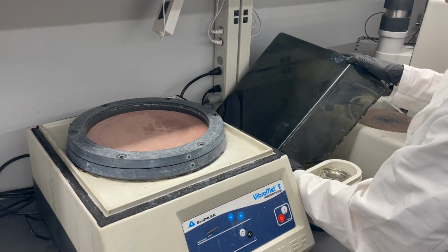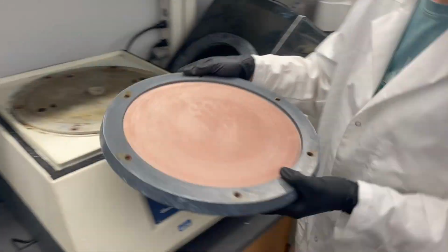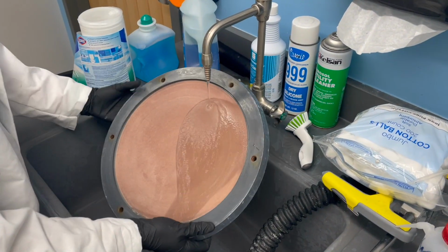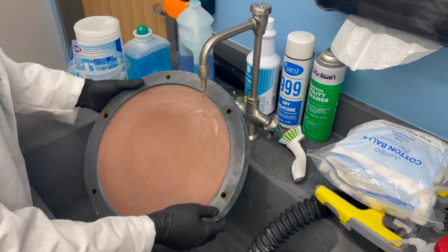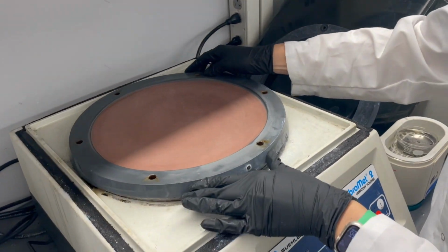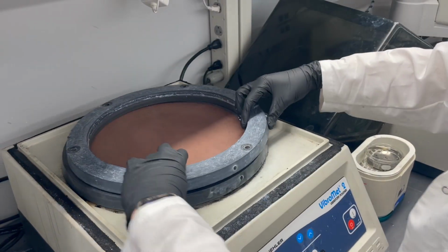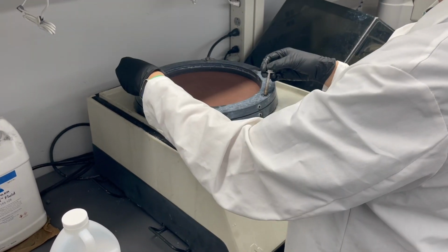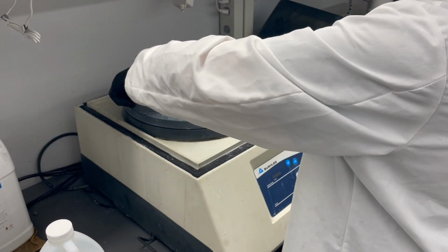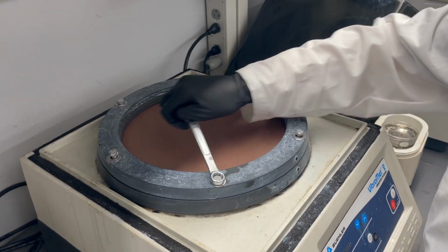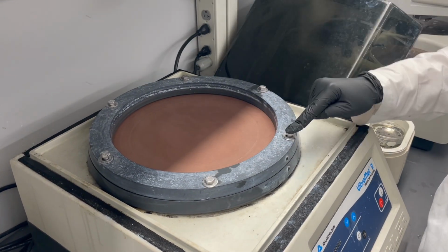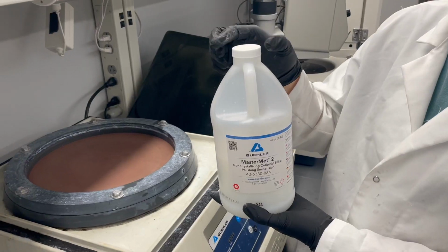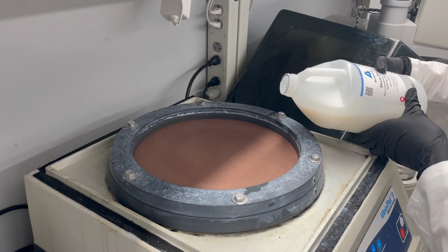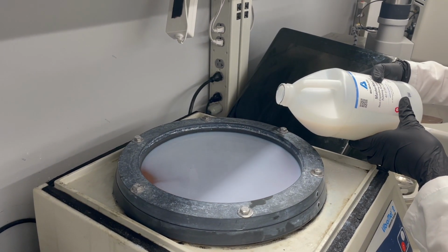While the ultrasonic cleaner is running, prepare the vibratory polisher. Remove the pieces from the machine and bring the pad over to the sink to rinse. Place it on the polisher with the indicator facing you. Align the top ring using the indicator. Put the bolts in their designated spot and use the wrench to tighten them in a star pattern to ensure an even seal. Pour a layer of the non-crystallizing colloidal silica until it just covers the polishing pad.